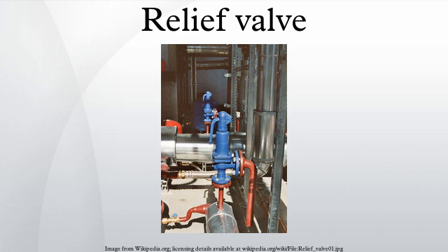In high-pressure gas systems, it is recommended that the outlet of the relief valve is in the open air. In systems where the outlet is connected to piping, the opening of a relief valve will give a pressure build-up in the piping system downstream of the relief valve. This often means that the relief valve will not reseat once the set pressure is reached.